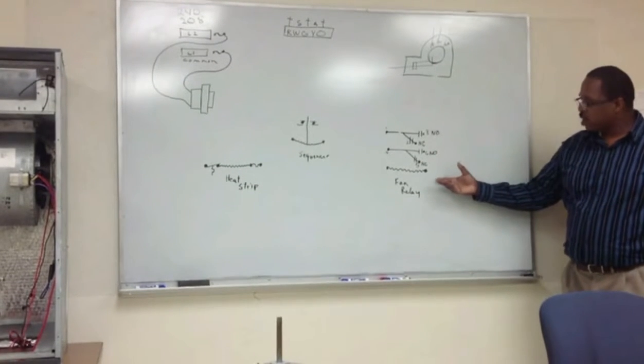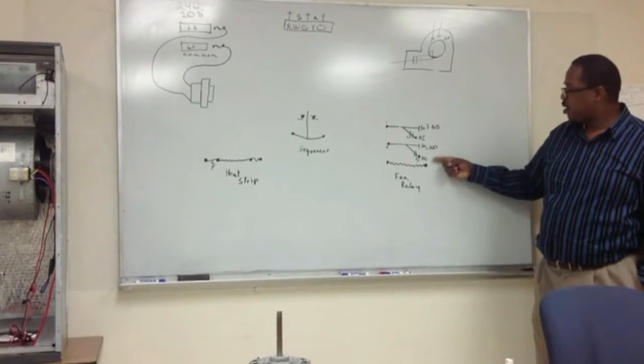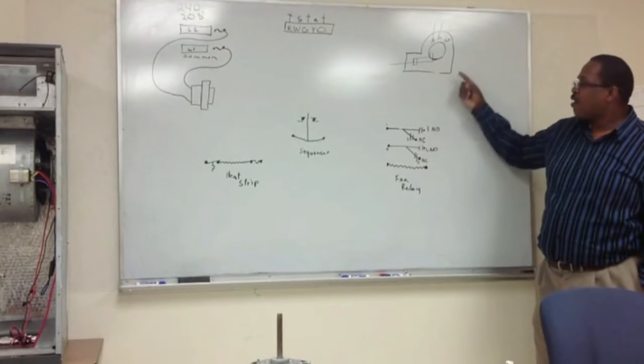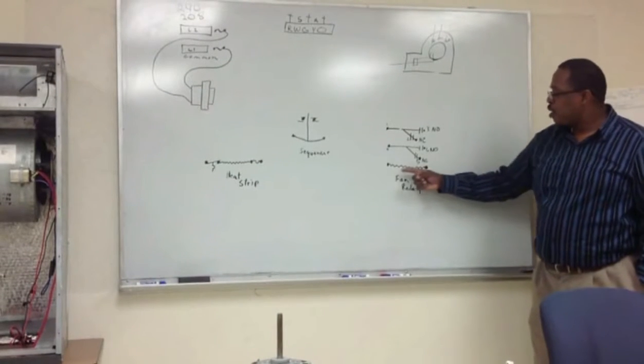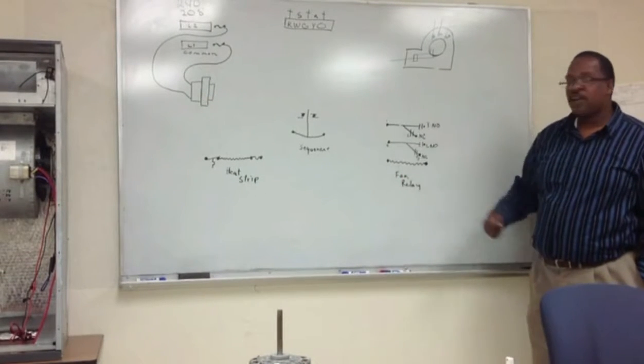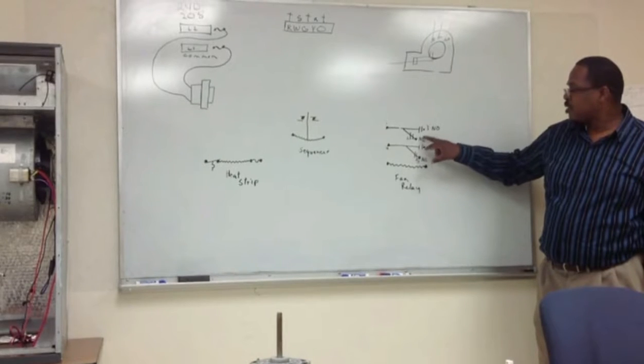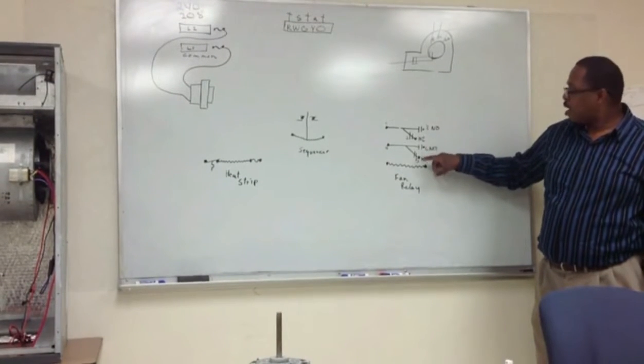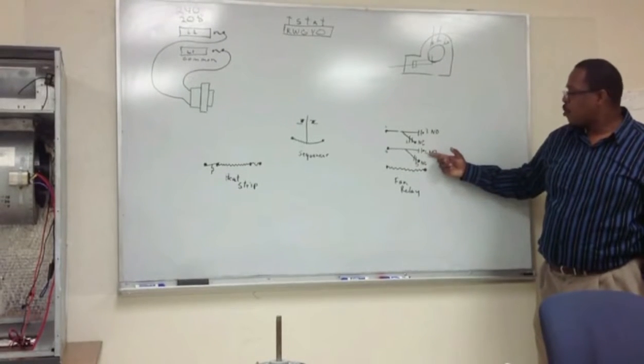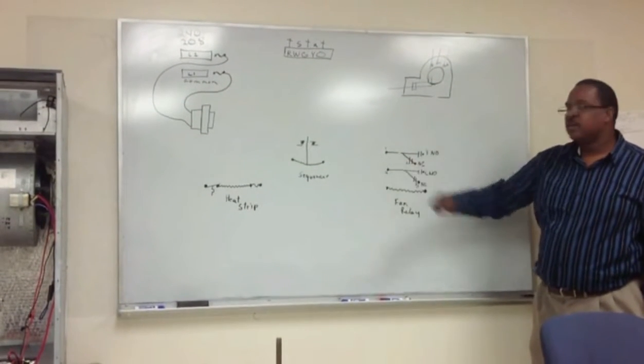Anyway, we were talking about how to wire up a fan relay. Now, we mentioned here you got normally open contacts and normally closed contacts. You have three circuits. The two circuits up top are what you would use or what we call the switching circuits. What we use to send power to and from our fan relay. And the bottom is where our low voltage controls will hook up. And this will energize or de-energize the fan relay. Now, when the fan relay is energized, our normally open contacts do what? Close. And our normally closed contacts open up. So that means they will stop power. Or normally closed when it's energized. Normally open will pass power when it's energized.